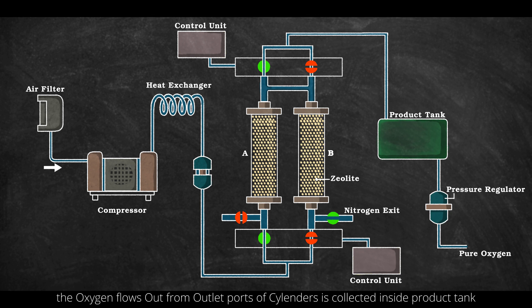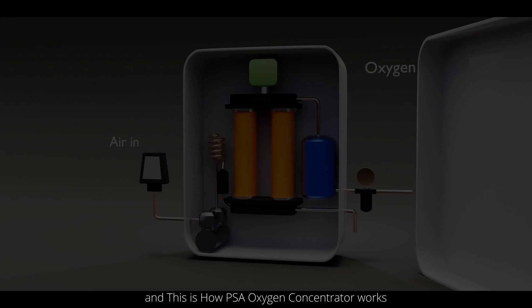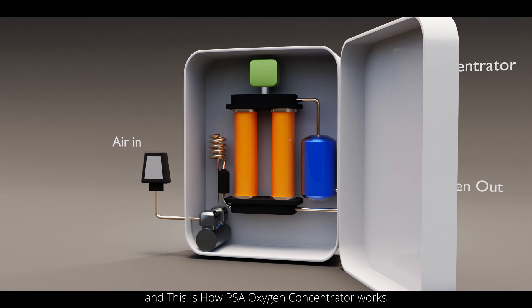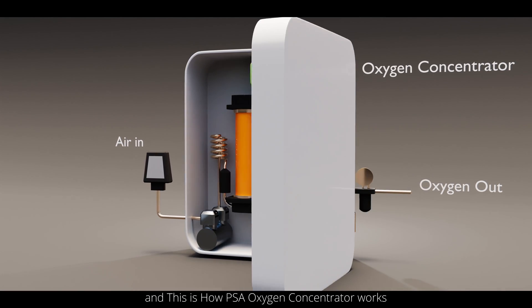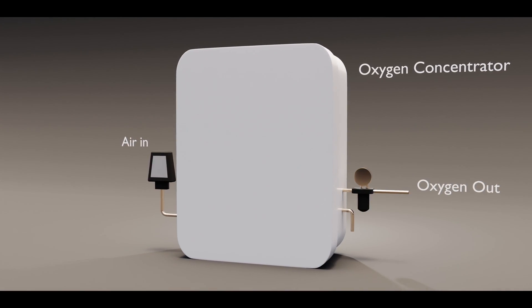The oxygen flowing out from the outlet ports of the cylinders is collected inside the product tank. It then passes through a pressure regulator and finally reaches the oxygen output delivered to the patient. And this is how a PSA oxygen concentrator works.